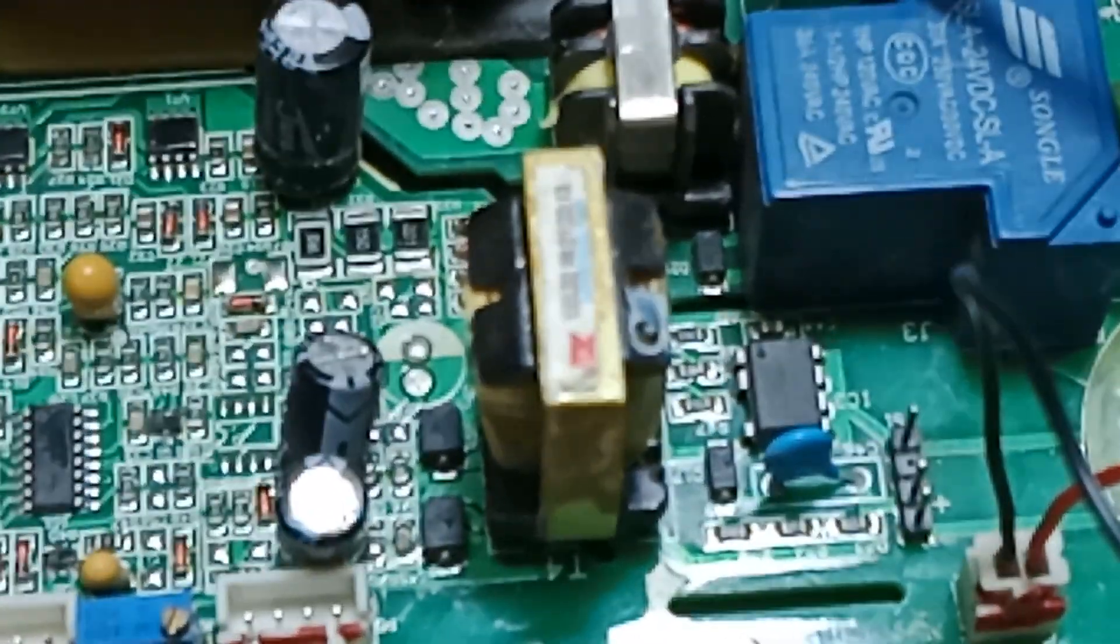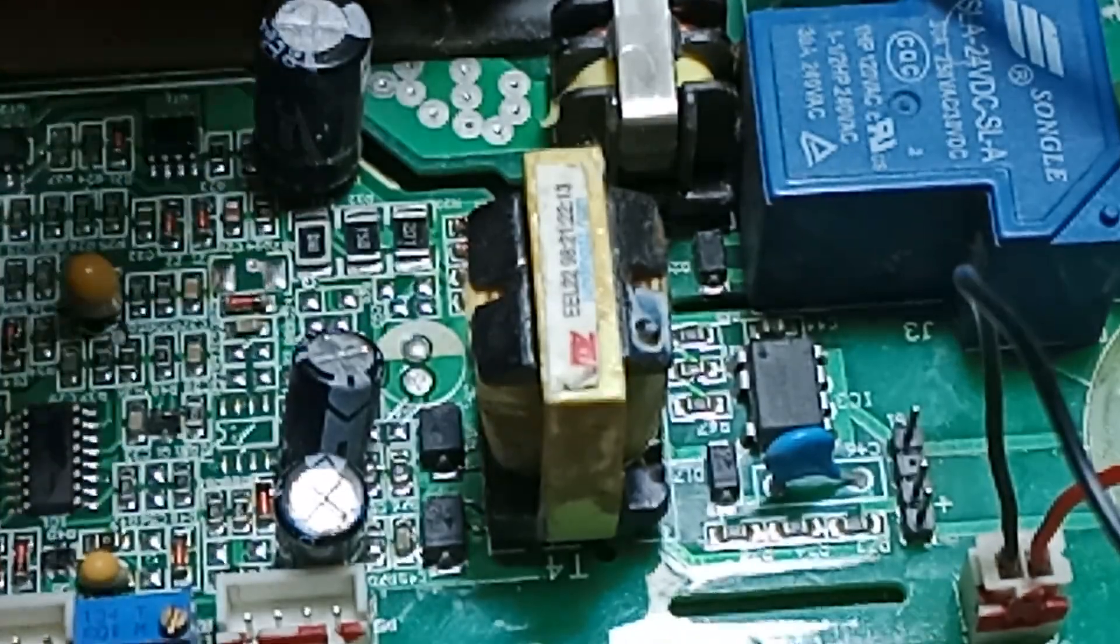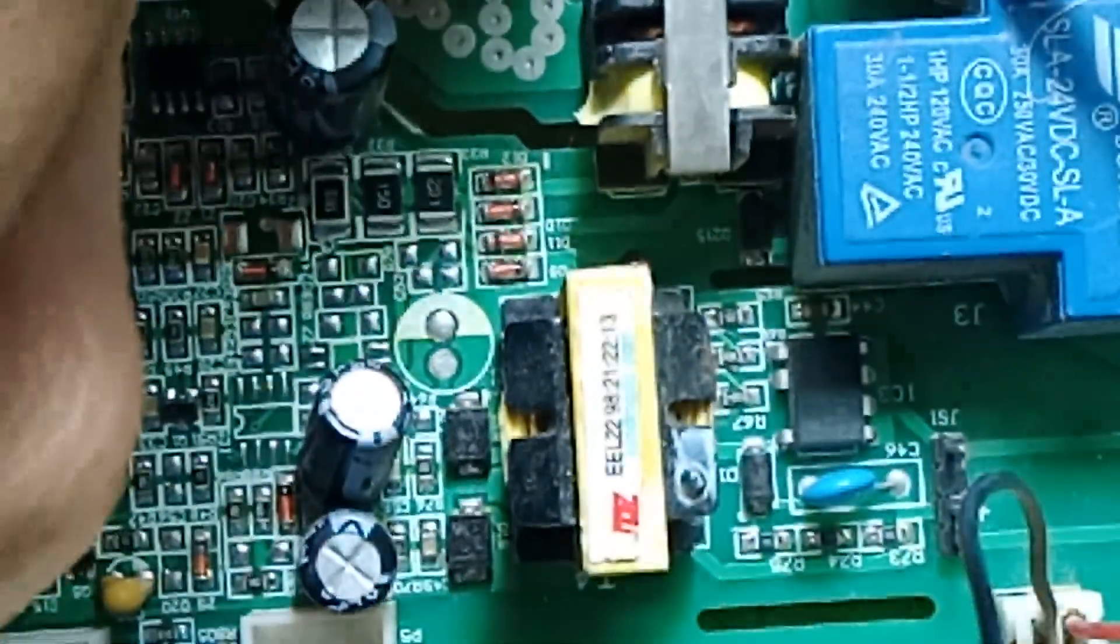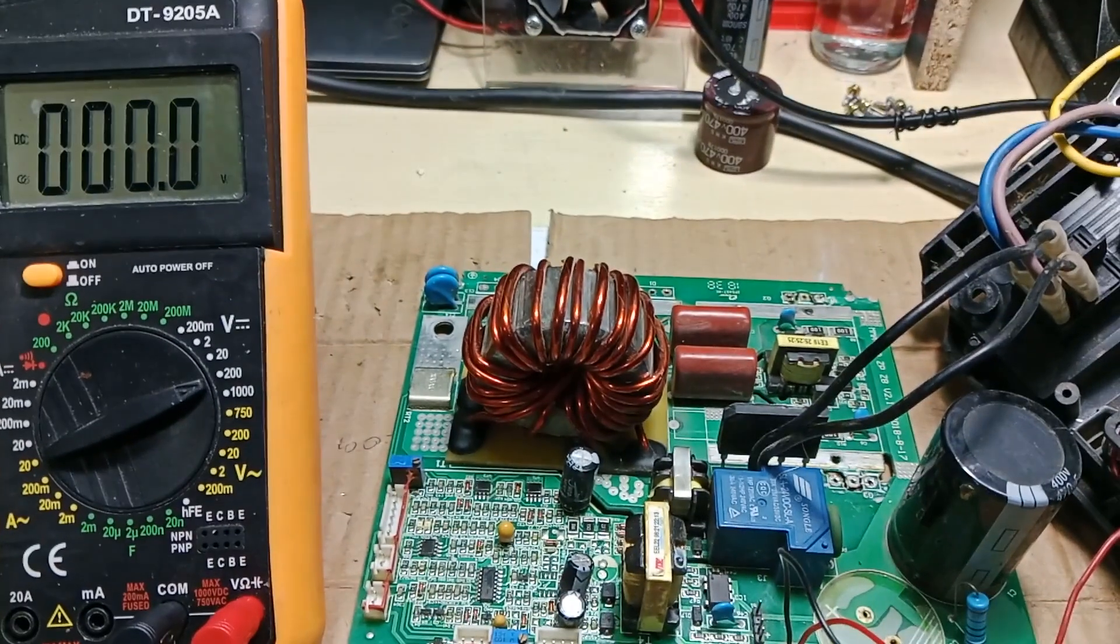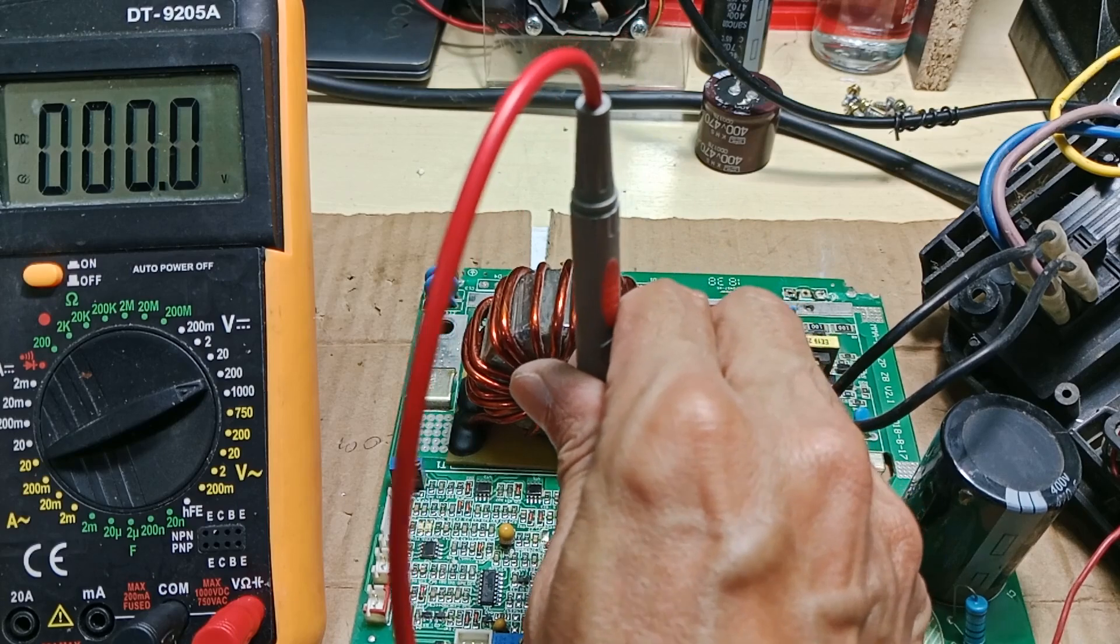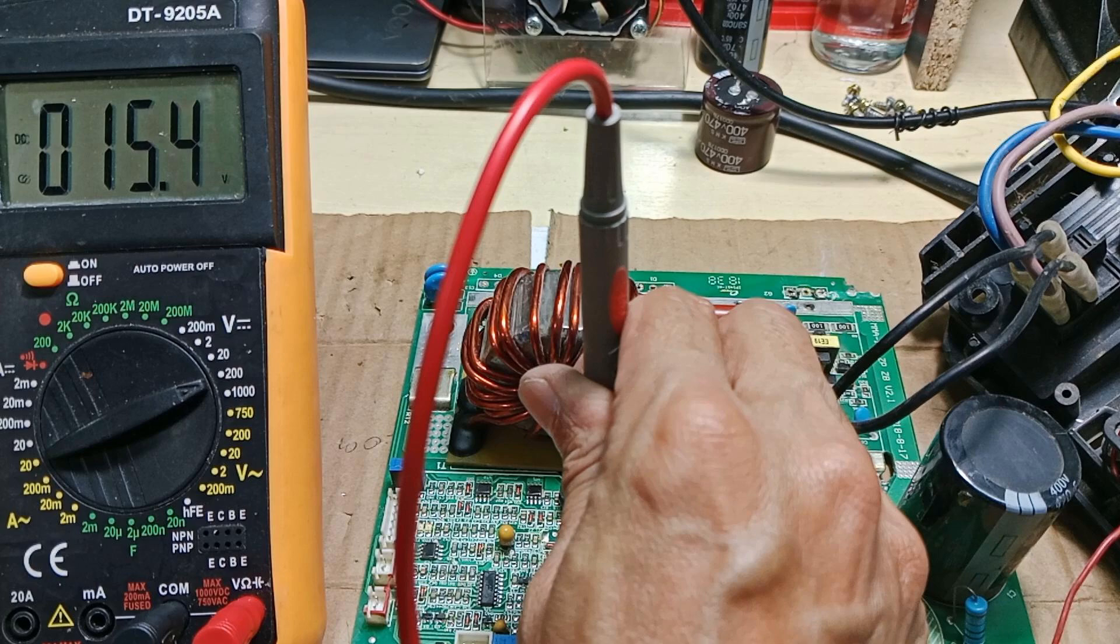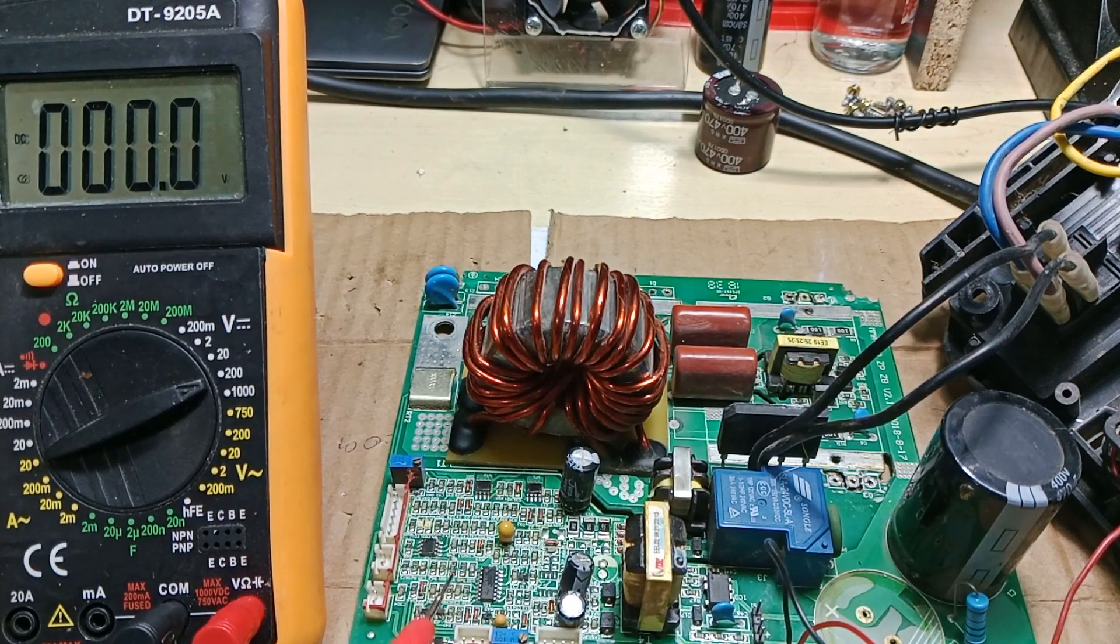Using a voltmeter, I check to see if there are the 24 volts and 15 volts output. You can see that I probed my test leads to the cathode of the two rectifier diodes right next to the auxiliary power supply transformer. And that is where we can check the output of the auxiliary power supply.